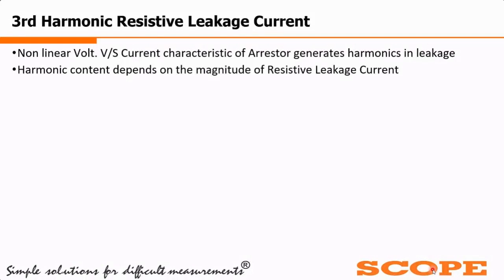Now, the point comes how the third harmonic resistive leakage current is coming into the picture, or from where the harmonics are getting generated. IEC or the researchers have come out with the conclusion that the nonlinear voltage versus current characteristics inside the arrestor is the main creator of the harmonics in the leakage current, because ZnO is supposed to work as a pure resistor in normal condition. So it is very much non-linear, and we are using the blocks. So non-linear voltage versus current characteristics inside the LA create the harmonics.